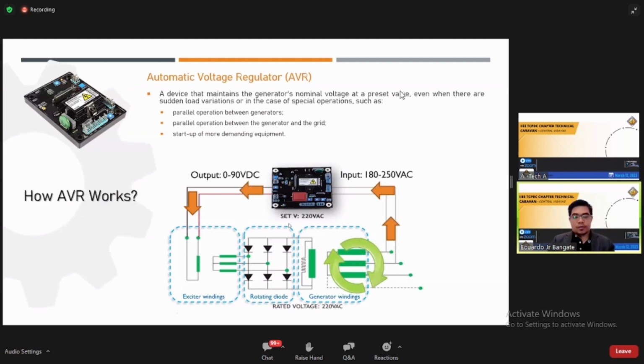If you rotate the generator, there is a residual current inside the alternator. This residual current gradually develops in the system, and it will provide the necessary input current and voltage to our AVR. Now, our AVR has something called a triggering voltage. It will not operate until the triggering voltage is reached or exceeded. So if you don't have the triggering voltage, there will be no output.